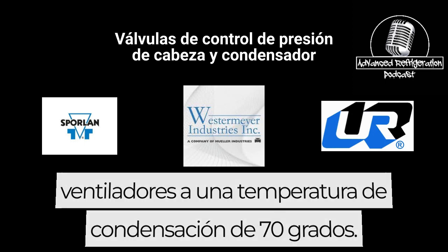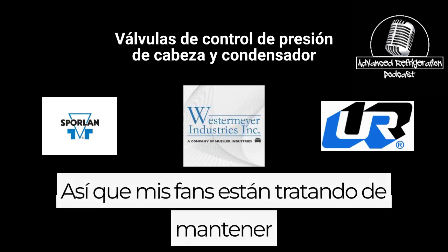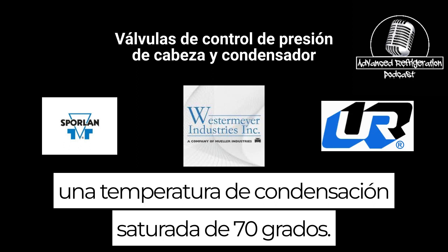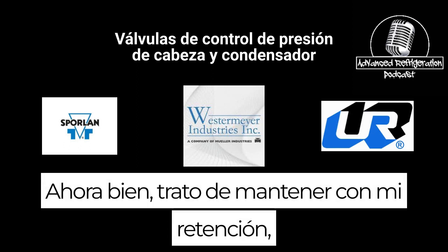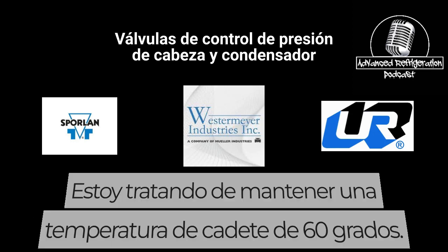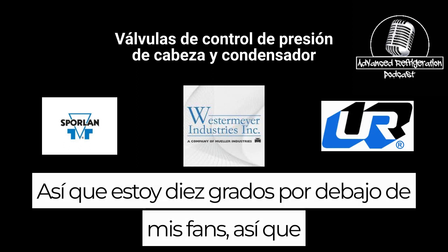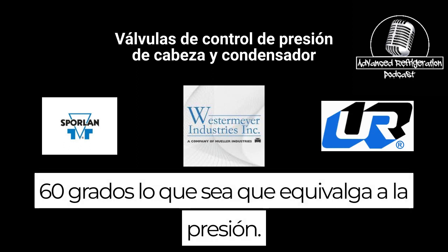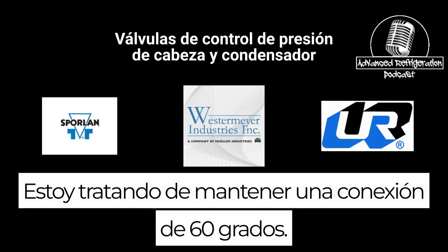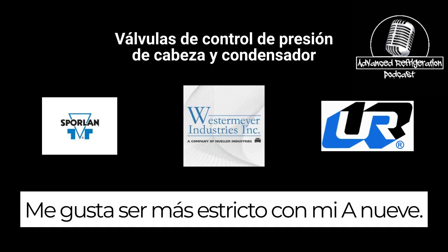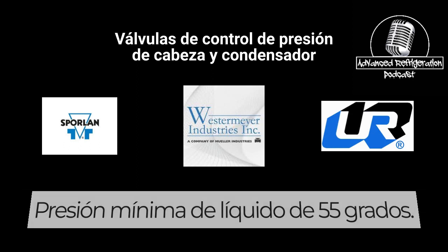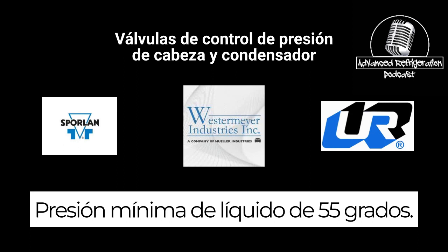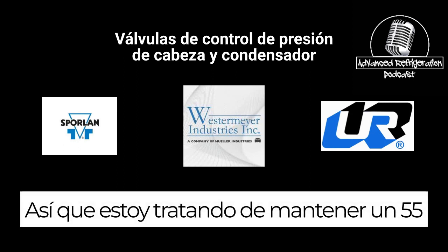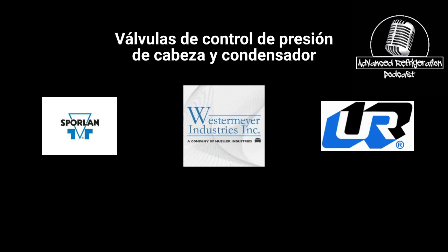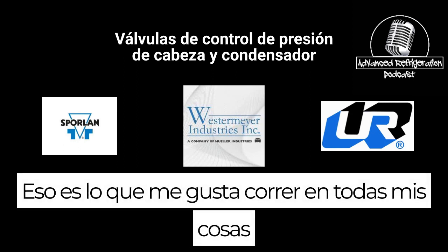Now, when I say that, I mean fans off. My fans are trying to maintain a 70 degree saturated condensing temperature. Then with my holdback, I'm trying to maintain a 60 degree condensing temperature, so I'm 10 degrees under my fans. Whatever 60 degrees equates to in pressure, that's what I'm maintaining. And I like to get tighter with my A9s. I'm trying to maintain a 55 degree minimum liquid pressure. That's what I like to run on all my stuff.